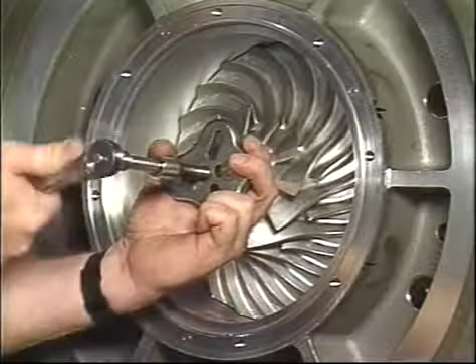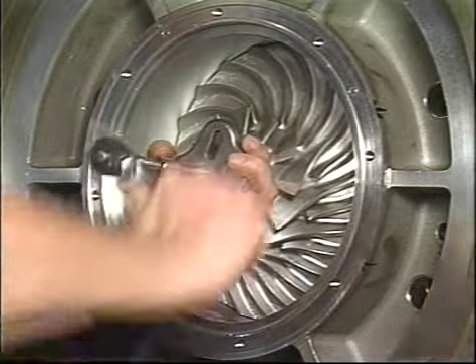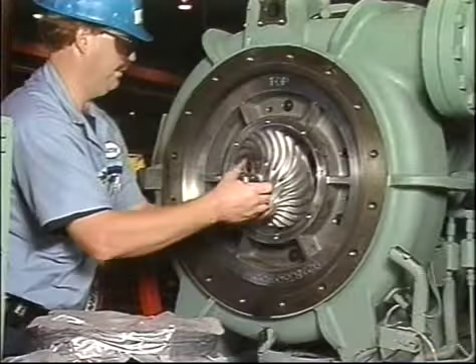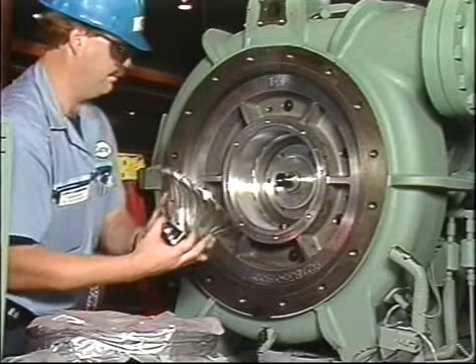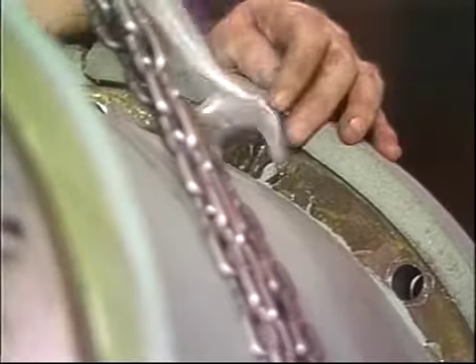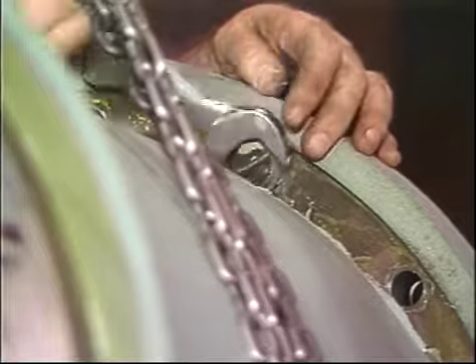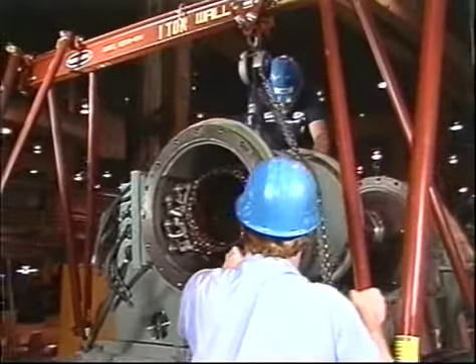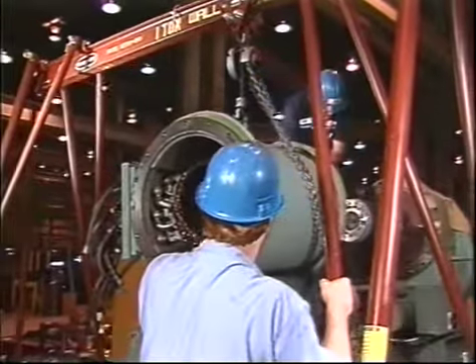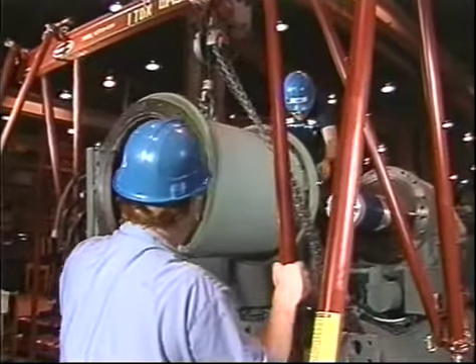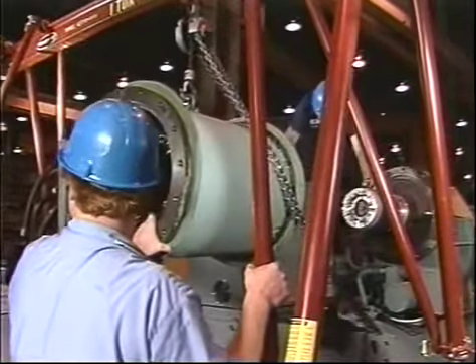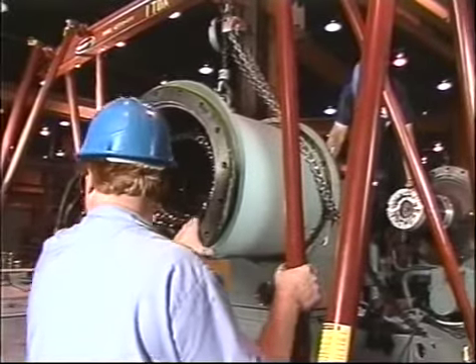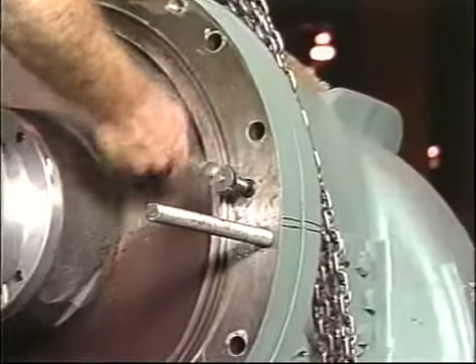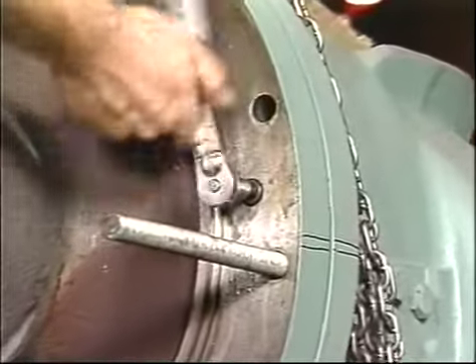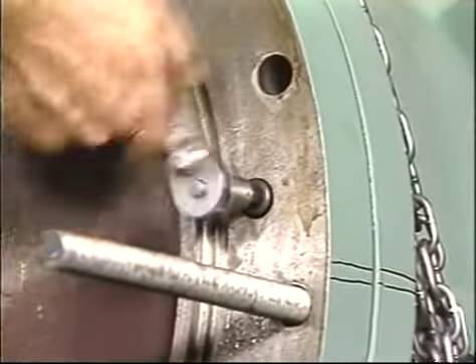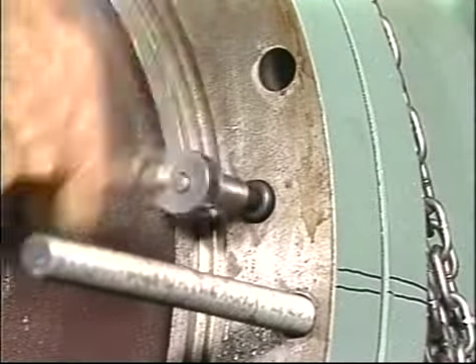Now we need to talk about maintenance. The sad truth is that when our technicians are called to fix machines with major problems, they often find that these problems are due to poor maintenance. If you let the machine run itself and wait for problems to develop, problems will indeed develop. But if you maintain it well, your chiller should give you many years of continuous duty. It's always more costly and disruptive to deal with an emergency breakdown than to provide maintenance on a planned schedule.